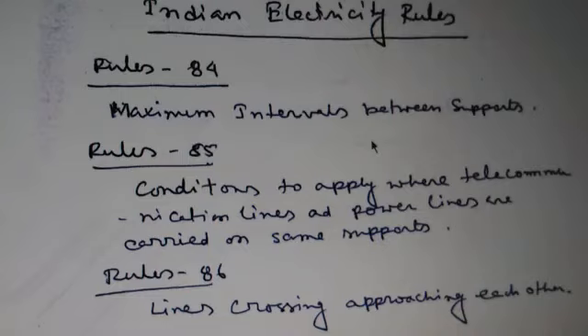Next point, every telephone used on the telecommunication line erected on a support carrying a power line shall be suitably guarded against lightning and shall be protected by a cutout. Next point, where a communication line is erected on a support carrying a high or extra high voltage power line, arrangements shall be made to safeguard any person using the telephone against injury resulting from leakage of the system between such power and telecommunication lines.